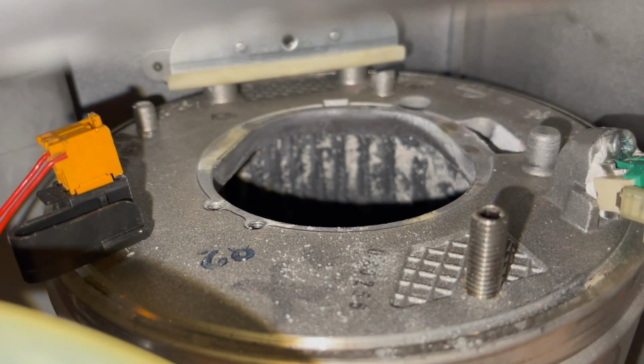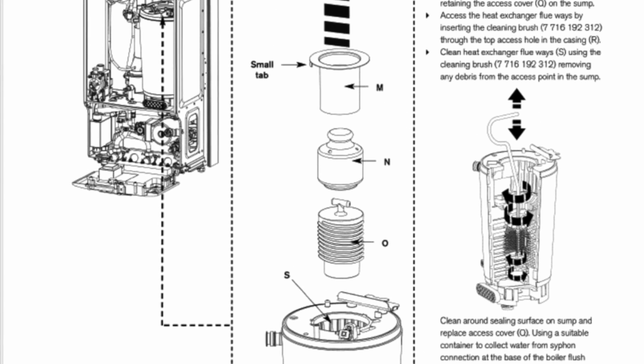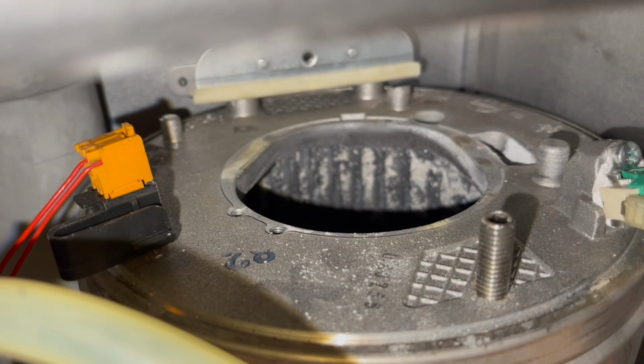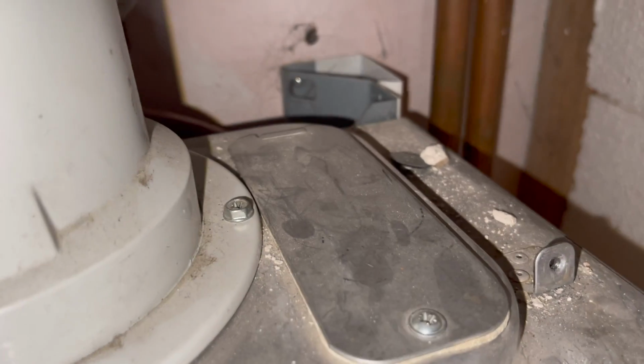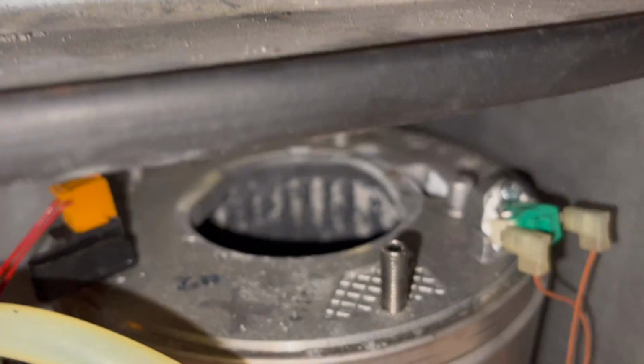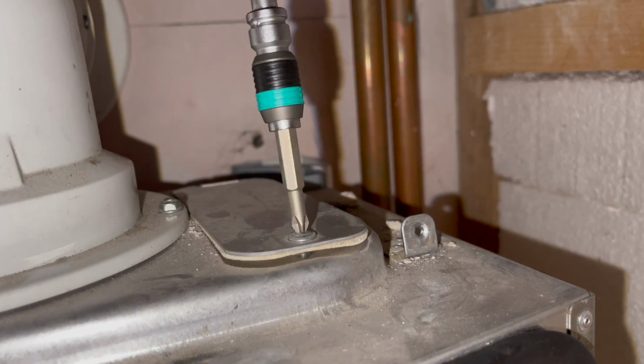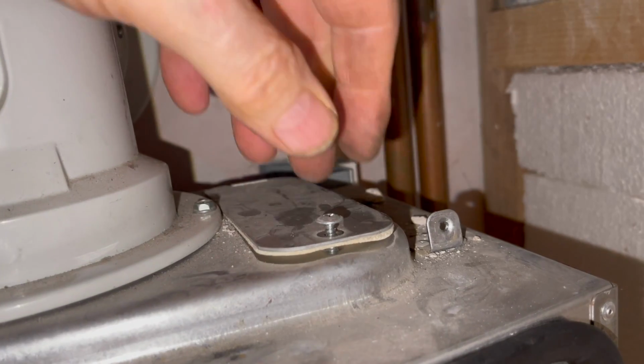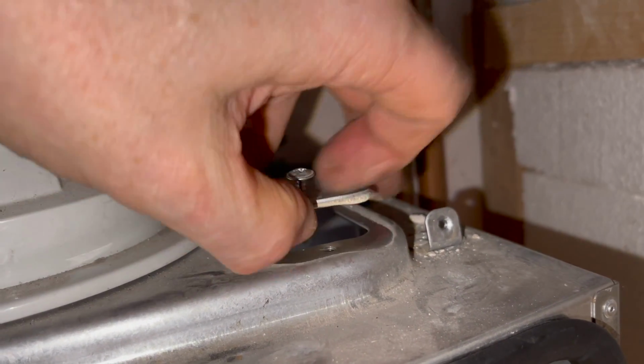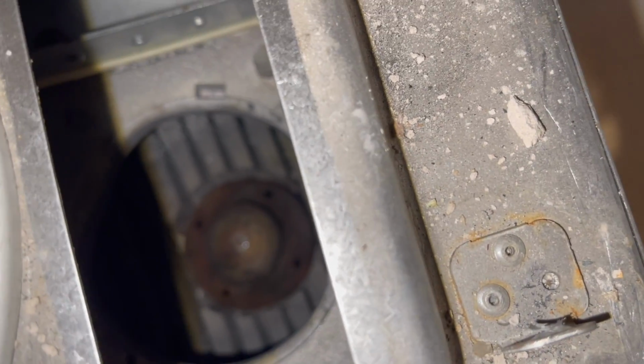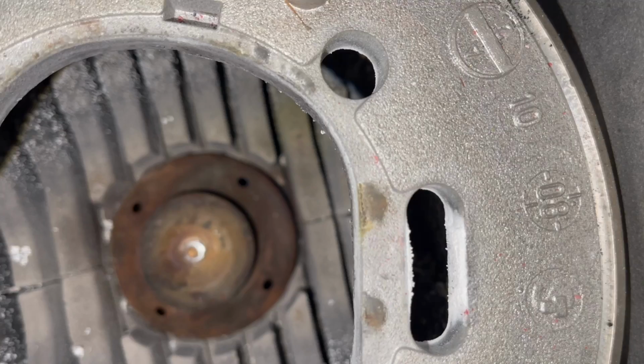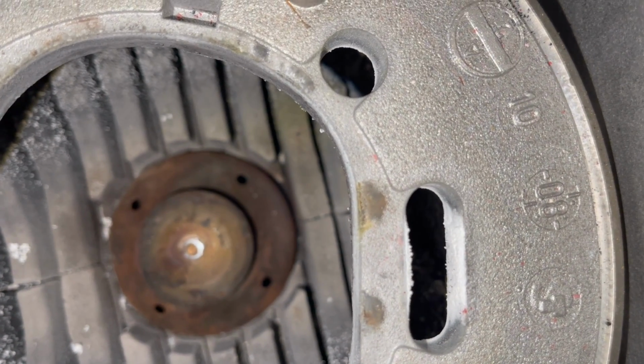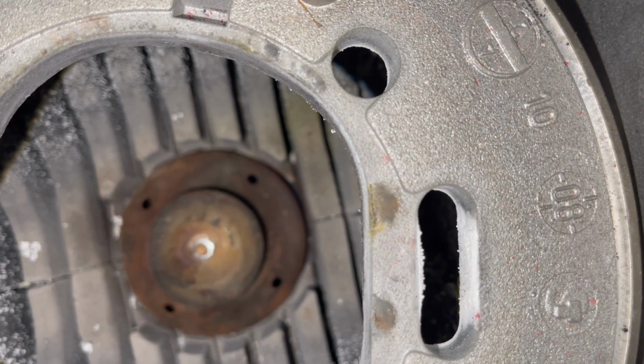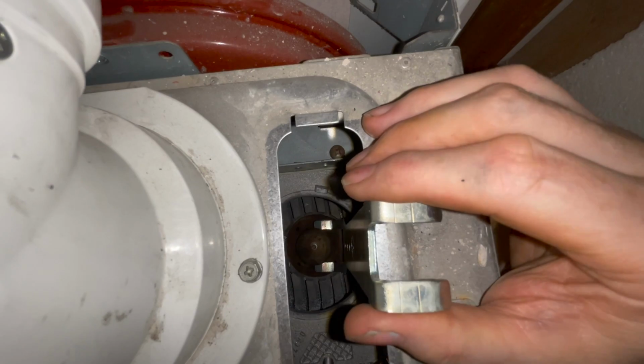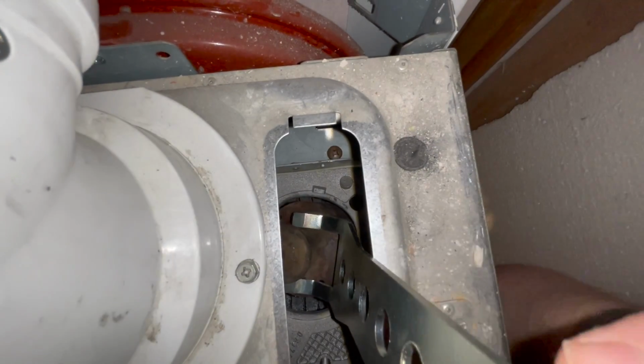Now inside there is a set of baffles. Now to get those out we need some specialist tools, which I've got, and I'll show them in a second, but we need to remove this plate on the top to allow the specialist tools to slide in. So we just need to undo this screw. Remove the plate, and we should be able to get into there so we can get the baffles out. So you can see the first baffle there, what we've got to get out. So we need to get this special spanner to remove that one. So hopefully you can see this spanner has gone on to the first set of baffles, and we can remove that.